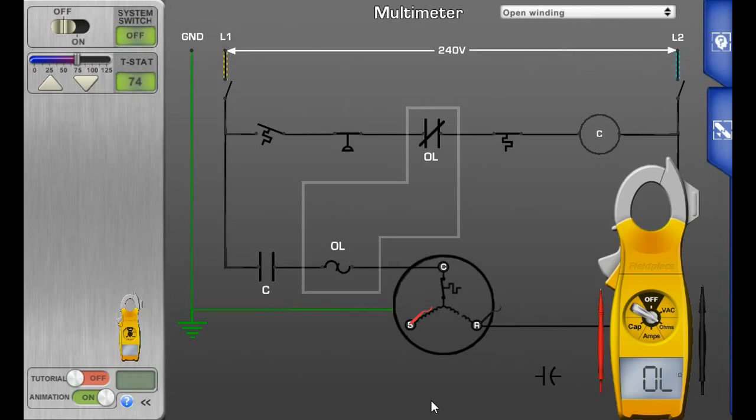You always got to make sure—there's an awful lot of compressors that are condemned for an open winding because the internal overload is open due to overheating. Let's look at that one more time. Common to run: overload. That shows an open. What you want to make sure is that the internal overload is not tripped, so you're going to go start to run.